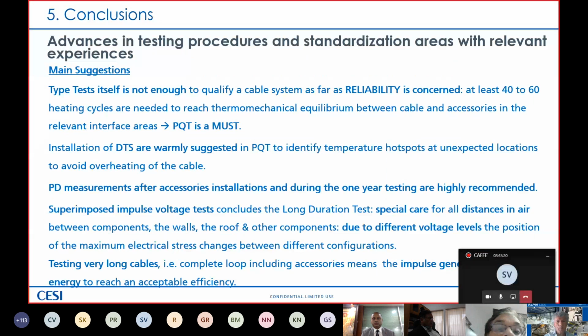What are the main suggestions I would like to share with you? Type test itself is not enough to qualify a cable system as far as reliability is concerned. At least 40 to 60 heating cycles are needed to reach thermomechanical equilibrium between cable and accessories in the relevant interface areas. So PQ test is a must.